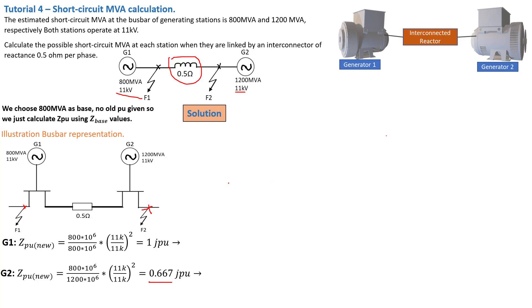We still have one thing to calculate — the per unit of the line. From generator 1 to generator 2, we have an interconnected line. Because it's a large system with very high potential short circuit current, that is why we included the reactor of reactance 0.5 ohm to limit the value to a safe level. Now we need to convert this reactor's reactance into a per unit value because it's an impedance. We consider that this 0.5 is the Z actual. The Z per unit of the line is Z actual divided by Z base, following the common per unit formula.